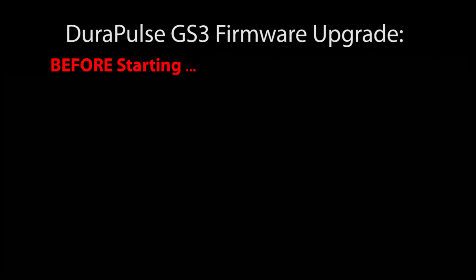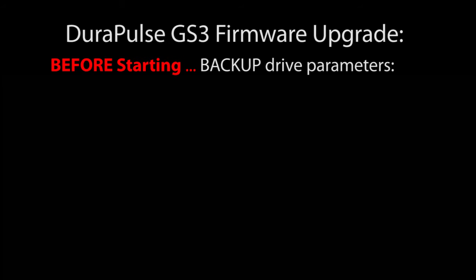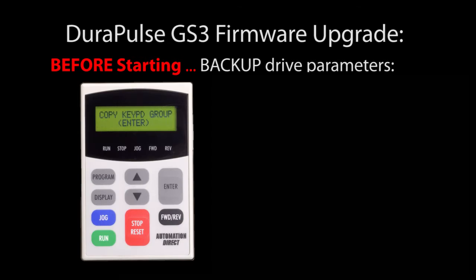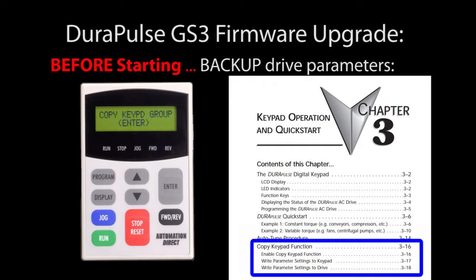Before we get started, I want to encourage you to backup the drive parameters. This firmware upgrade procedure doesn't overwrite any of the drive parameters, but why risk it when it only takes a couple of seconds to backup the parameters to the keypad. Chapter 3 of the user manual tells you how to do that. The cool thing about this is you can use one master keypad to update all of your drives and since the keypad is always there, you are guaranteed to have a backup solution handy.